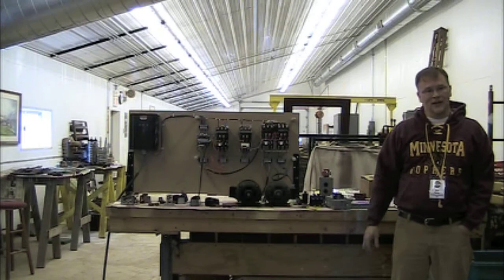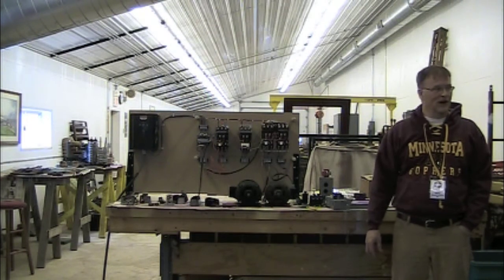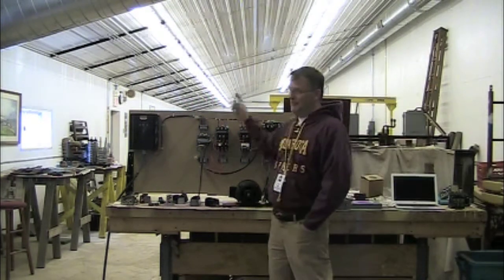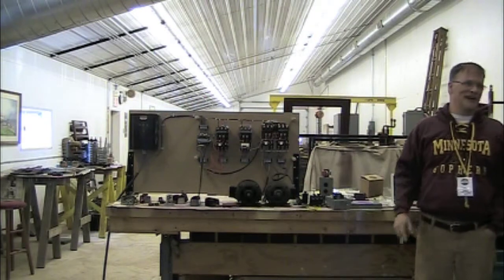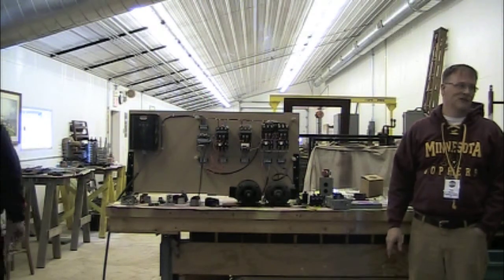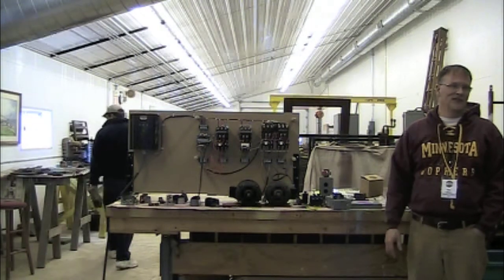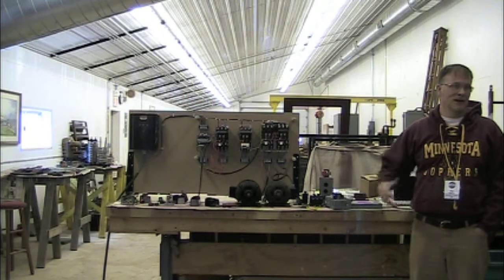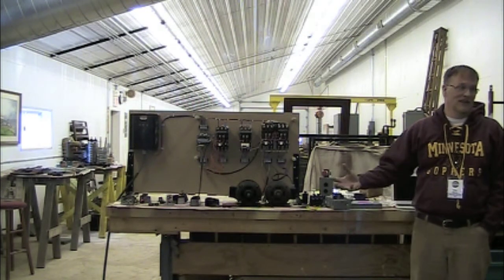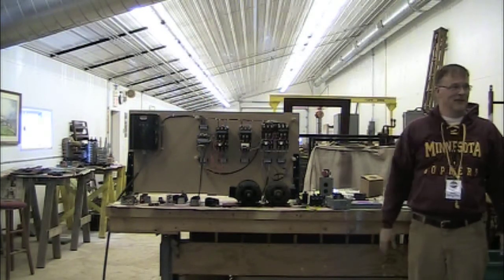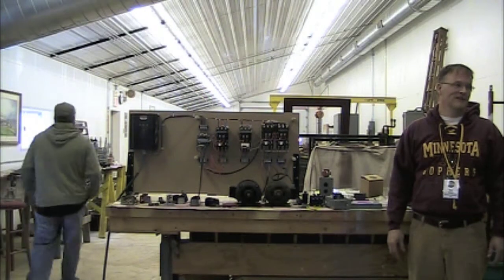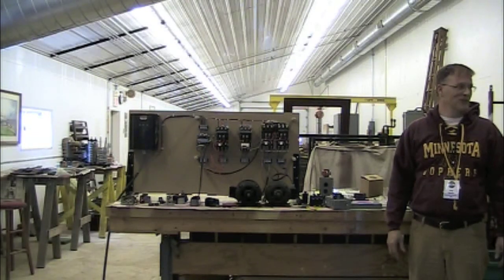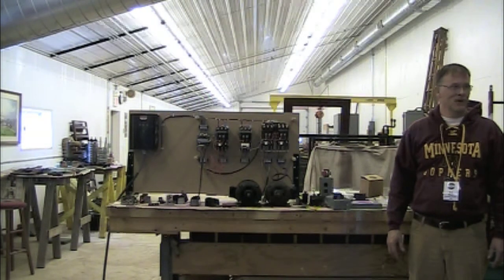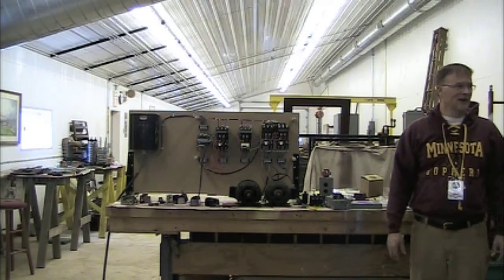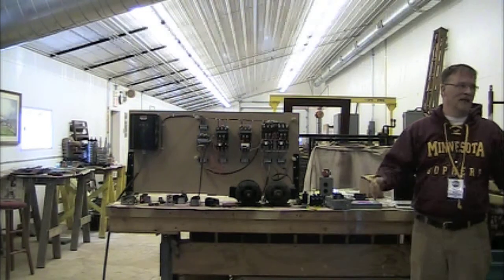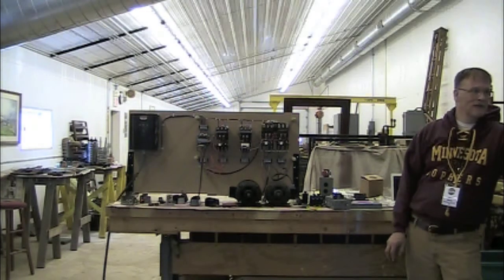And also, in the OSHA industrial world, most everything's done with control transformers too, because there are also limits on the amount of available fault current upstream of you that you can tie a control operator interface to. So in most cases, they just end up needing a control transformer to meet OSHA regulations. It's industrial safety stuff. It isn't in the NEC. It's in the other NFPA 70E and 79 that dictate that stuff. It's not a code issue, but in the industrial world it's imposed upon you. At our university, we have all kinds of old machines that are grandfathered, with 240-volt controls or whatever. But anything new they do, they have to follow the OSHA required stuff.